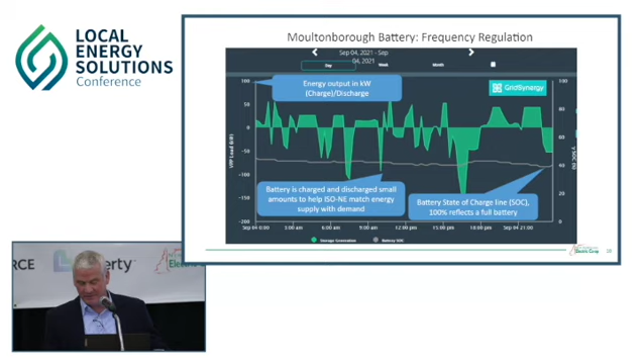This one's not so simple. This is what it looks like when it's on regulation. Regulation services are those where you're trying to meet supply and demand all the time, actually done on a 4-second interval. This view isn't on a 4-second interval, I believe it's on a 15-minute, or maybe a 5-minute interval. In each of these lines, you'd see the accumulation of whatever the battery did, in the area graph, the green.